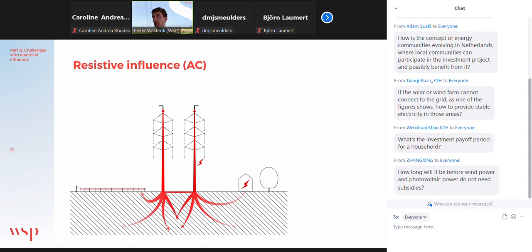Now, if you have, for example, a pipeline in the ground close to this point where the short circuit can occur, and by chance there happens to be a coating defect on the pipeline, or it's maybe an old degraded coating, or there is maybe some above ground part of the pipeline that is used to operate it, then the pipeline can assume the same high voltage of the soil at that location. Because it's conductive, it can bring this voltage far away from the location of the short circuit, where the potential of the soil is around 0 volts. And then you have maybe a voltage difference of 2000 volts between the pipeline and the surrounding soil.